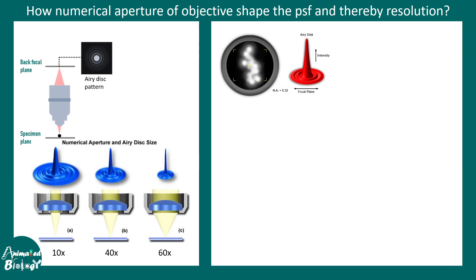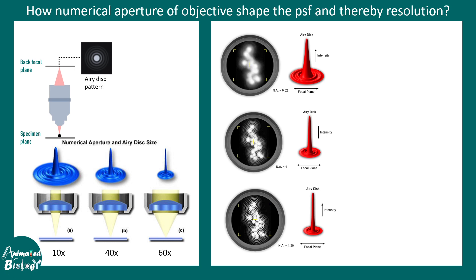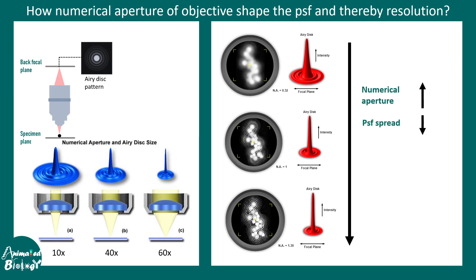Consider a collection of points rather than a single point object. At 10x with NA of 0.3 the image is not resolved — one cannot say how many points are in the image. As we increase the objective NA by going to 60x, one can now distinguish individual points. The point spread functions and intensity profiles become more crisp and sharp when NA is increased, reducing the overlap between individual PSFs. Greater the numerical aperture, smaller and crisper the PSF, the limit of resolution D decreases, and the resolving power increases.